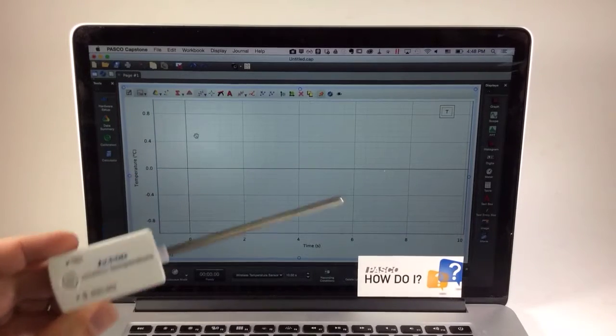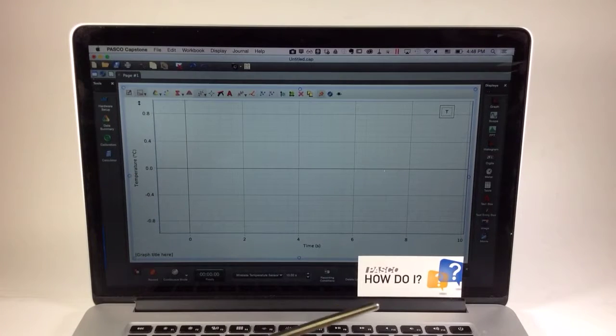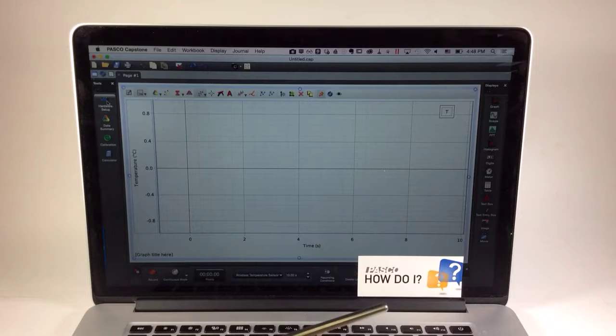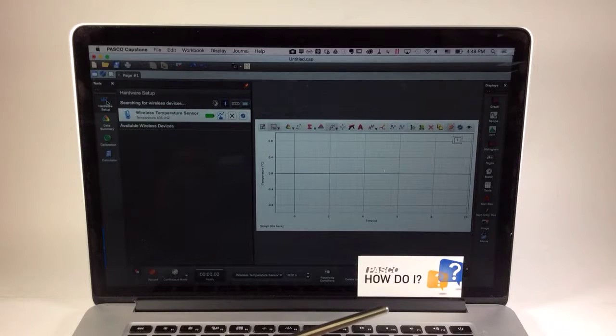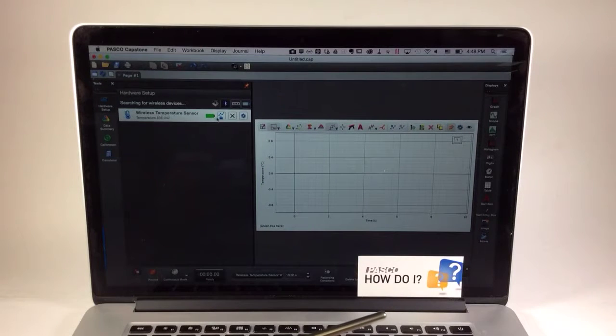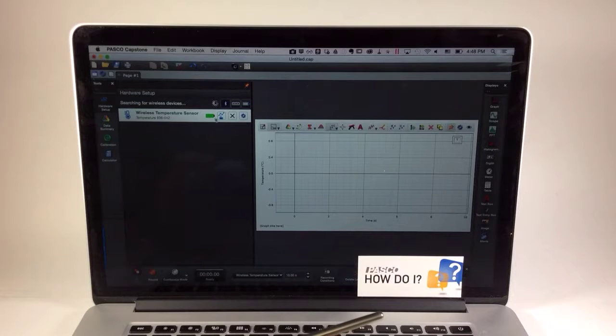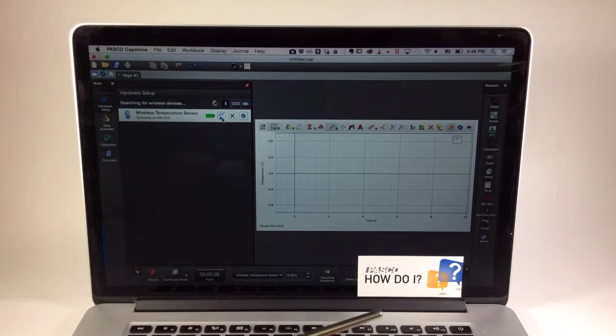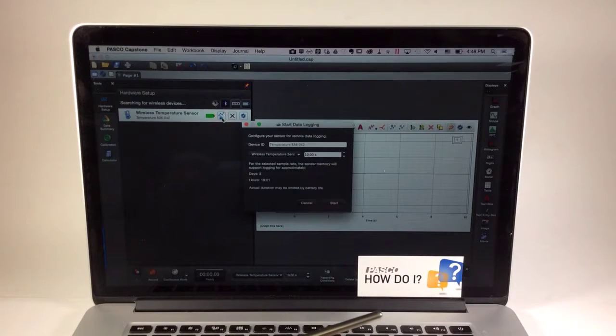To initiate remote data logging, I'm going to go into the hardware setup panel, locate my temperature sensor, and to the right of the battery status icon, simply press Start Remote Data Logging.